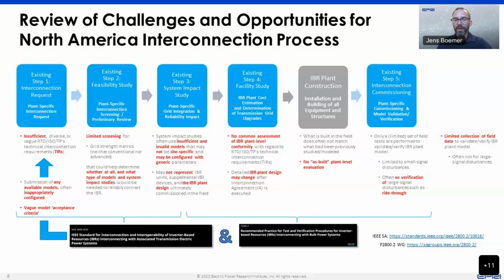In commissioning, it's quite tricky to actually run large signal disturbance tests without a lot of effort or impact on neighboring customers. So most of these commissioning tests are limited to small signal disturbances, and there's no verification of ride-through performance at all.